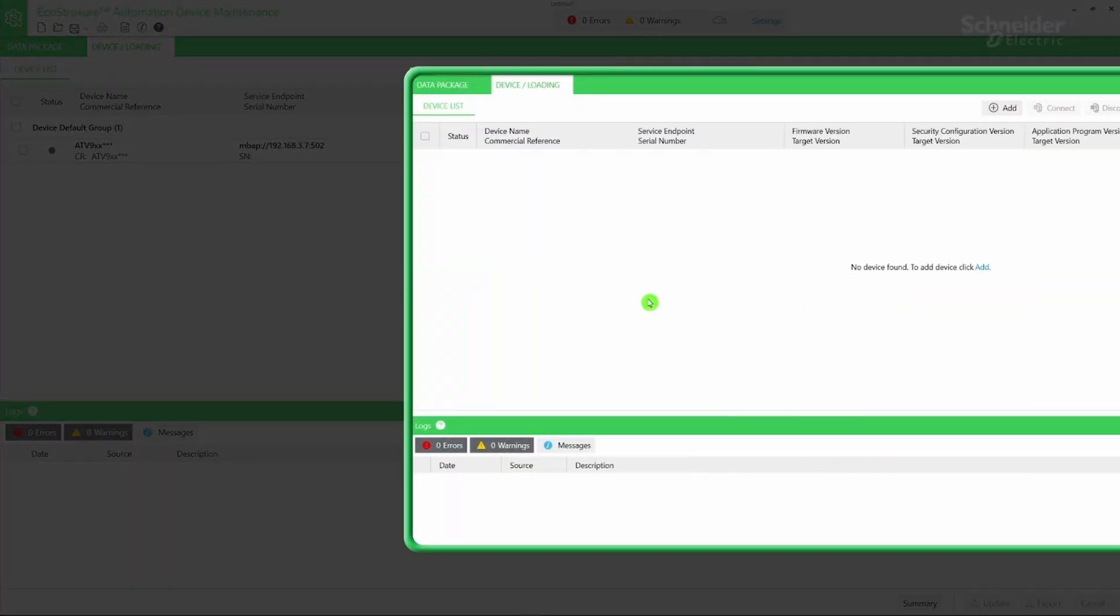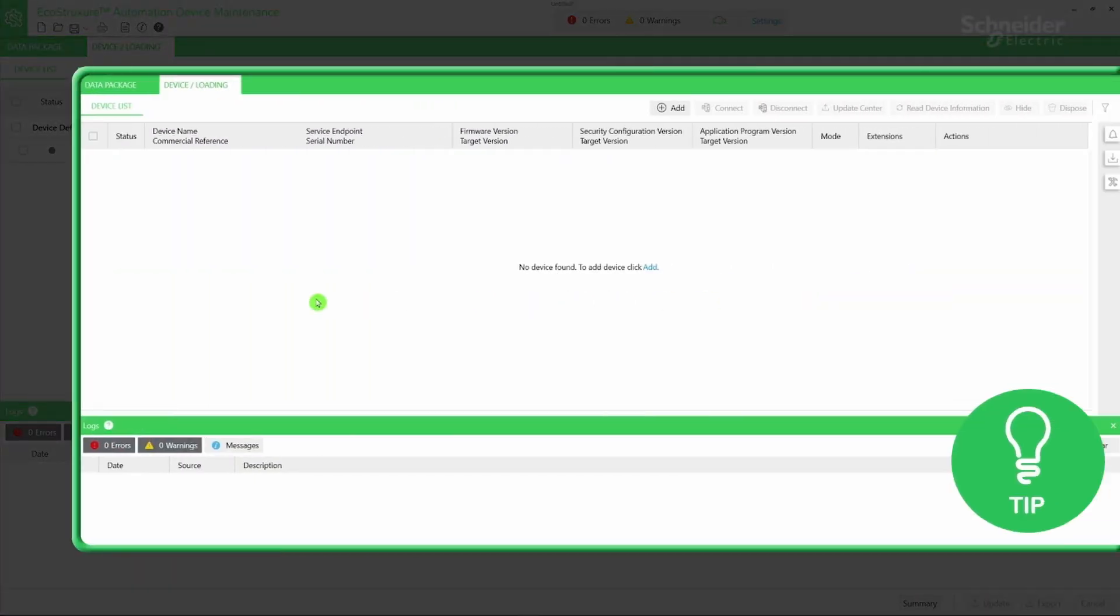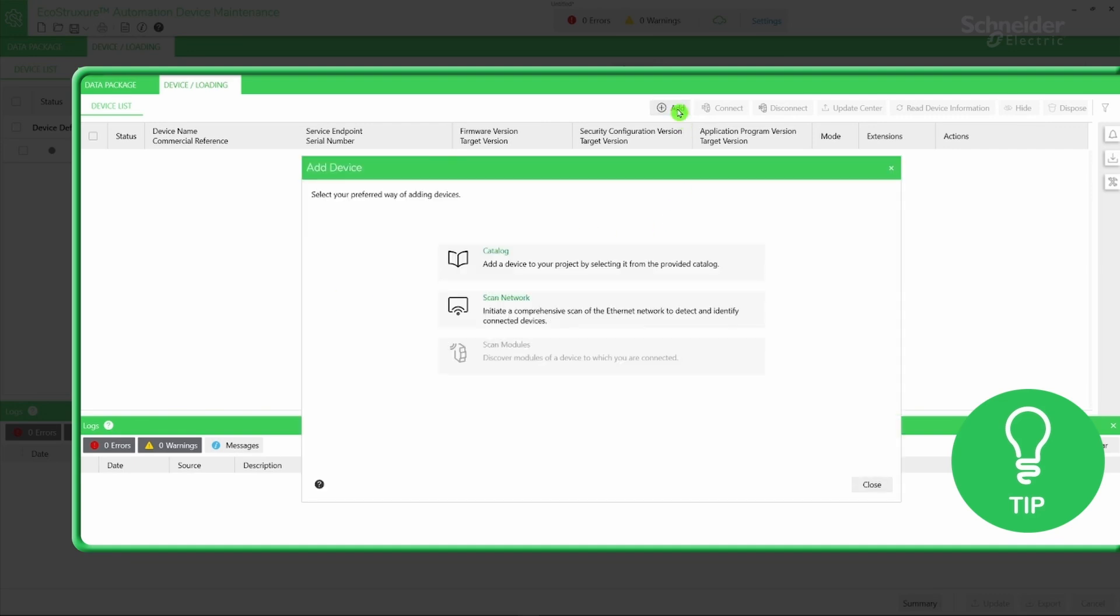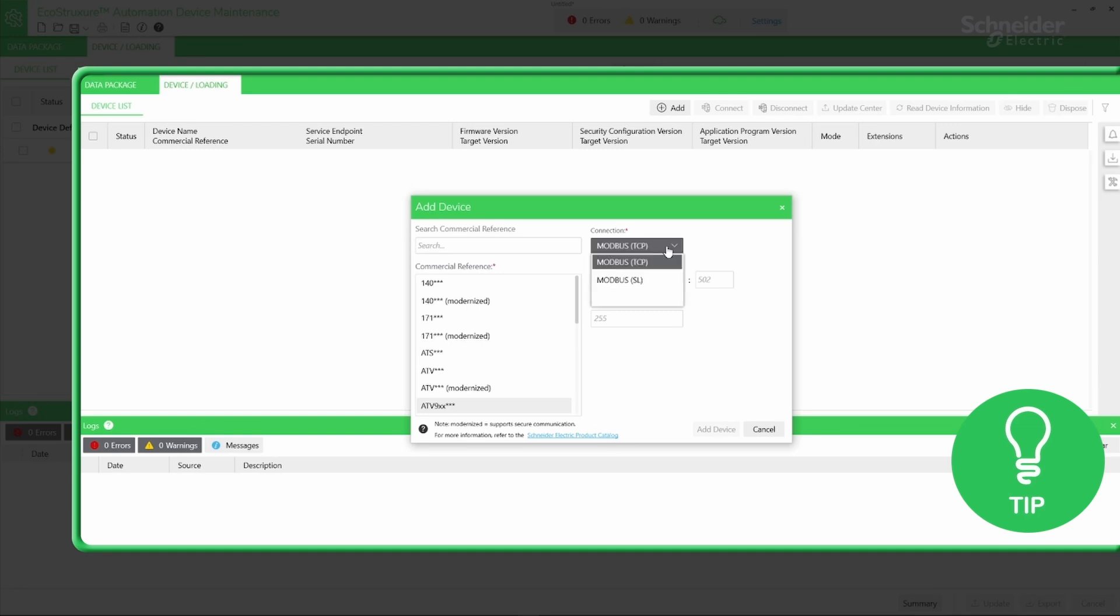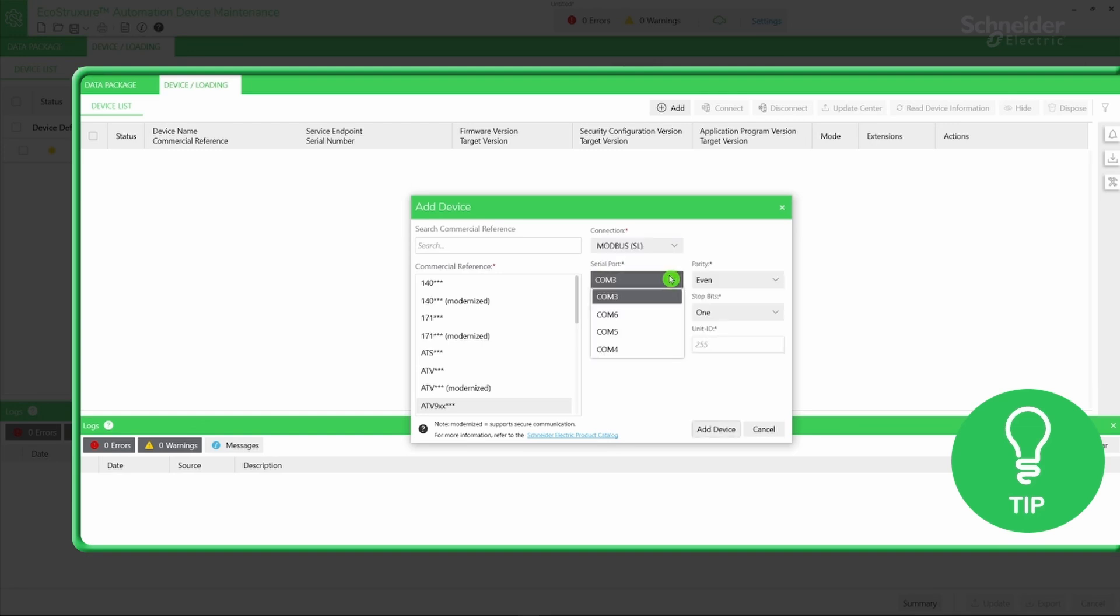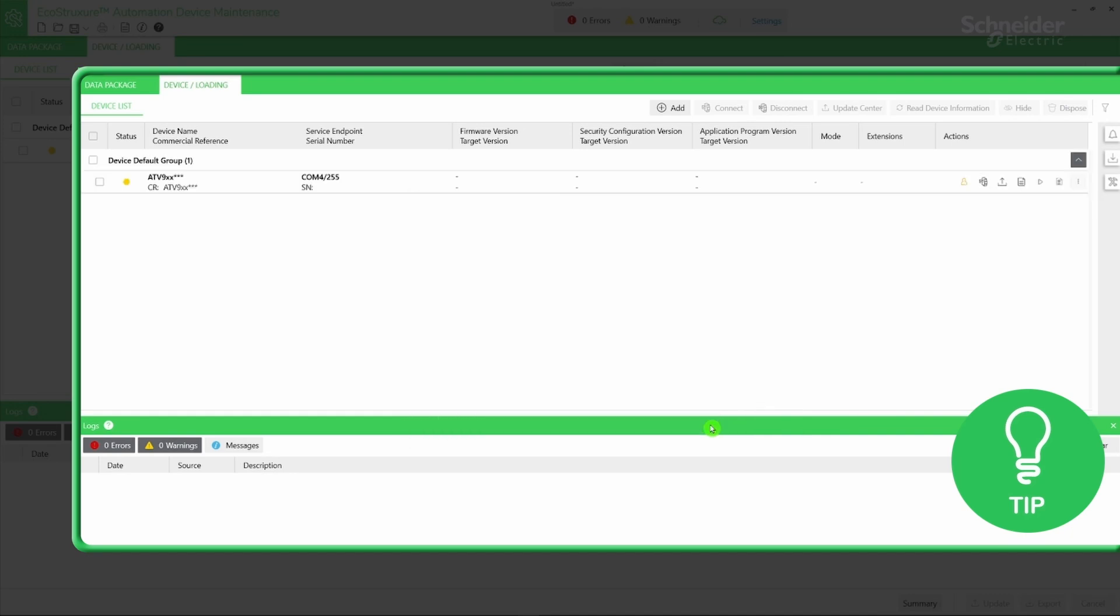Here is another little tip. If you're unable to add your device using Ethernet, you can add it using a Modbus serial line connection. To do this, click the add icon, then select Catalog. Next, select the commercial reference of your device. For the connection, select Modbus SL. Adjust the port settings based on the laptop port you're using to physically connect your device. Finally, click Add Device.